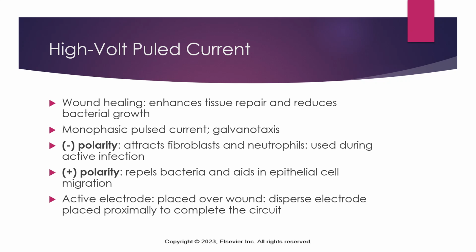Then we go to the positive polarity. When we're using a positive polarity, we are trying to repel bacteria and promote epithelial cell migration, making it beneficial for later stages of wound healing. So this can be switched to positive polarity once the infection is under control to optimize re-epithelialization.